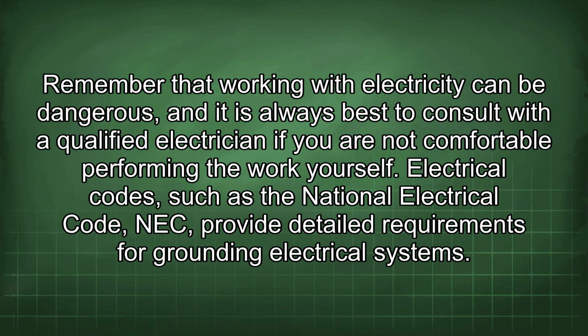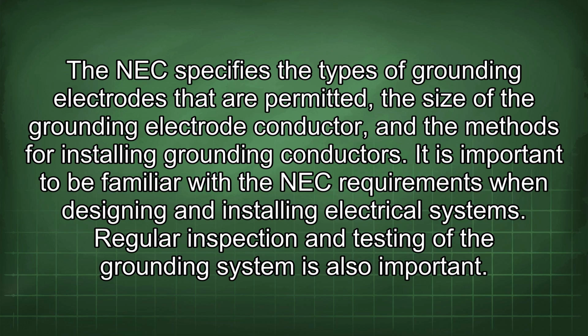Electrical codes, such as the National Electrical Code (NEC), provide detailed requirements for grounding electrical systems. The NEC specifies the types of grounding electrodes that are permitted, the size of the grounding electrode conductor, and the methods for installing grounding conductors. It is important to be familiar with the NEC requirements when designing and installing electrical systems.